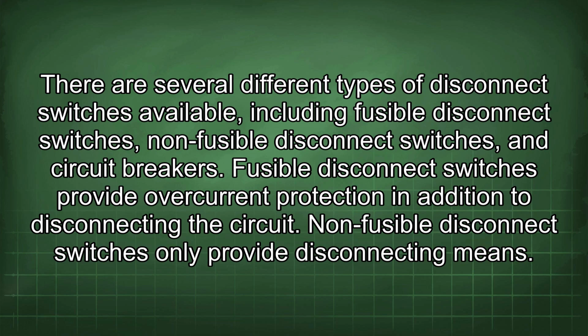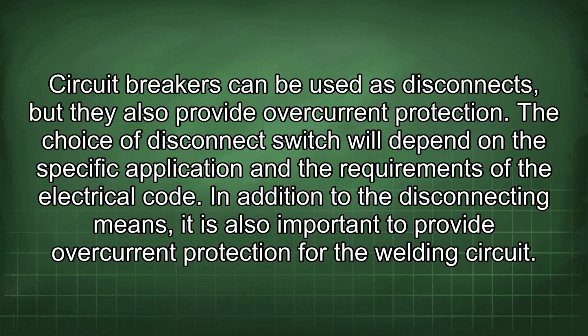Fusible disconnect switches provide overcurrent protection in addition to disconnecting the circuit. Non-fusible disconnect switches only provide disconnecting means. Circuit breakers can be used as disconnects, but they also provide overcurrent protection. The choice of disconnect switch will depend on the specific application and the requirements of the electrical code.